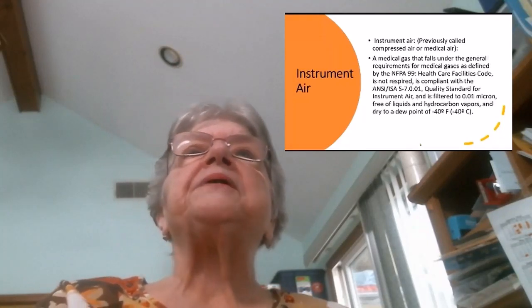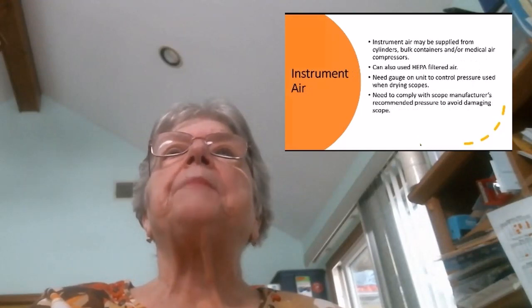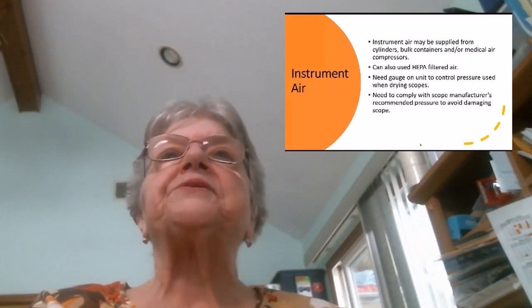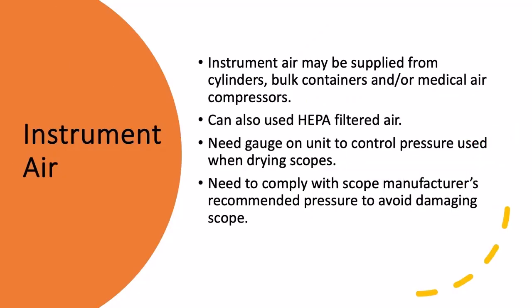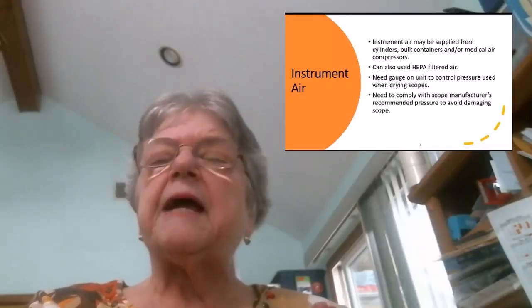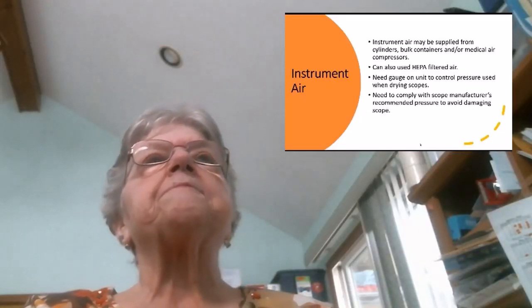Now, instrument air can be supplied from a bulk cylinder, bulk containers, or medical air compressors. You can also use HEPA filtered air. You should have a gauge on your unit to control the pressure when drying your scopes, and you need to comply with the scope manufacturer's recommended pressure to avoid damaging the scope. If the pressure is too high, you can damage the sheath on the scope.